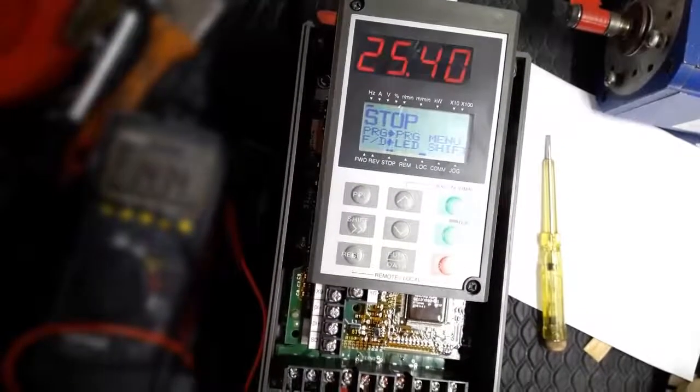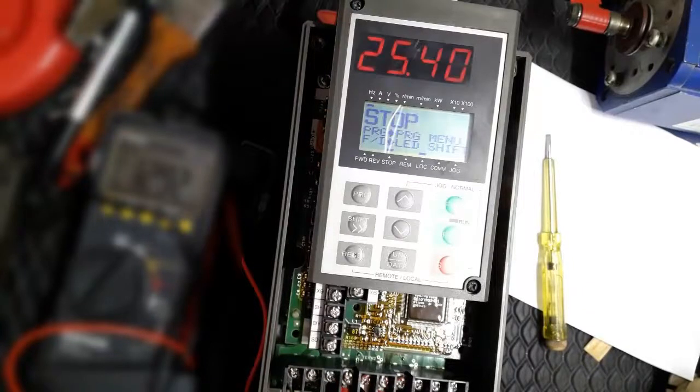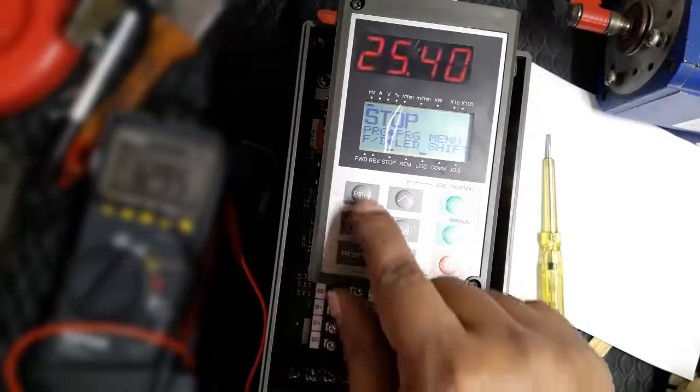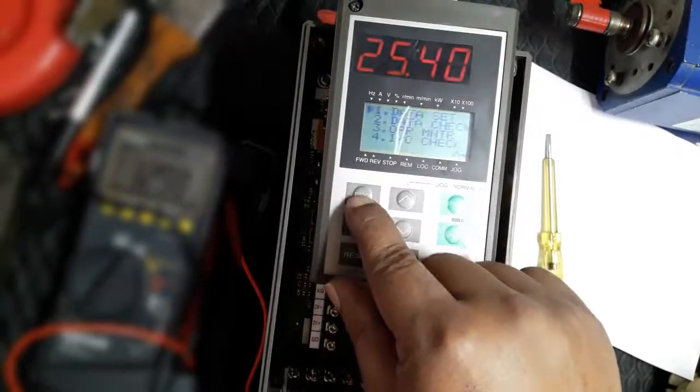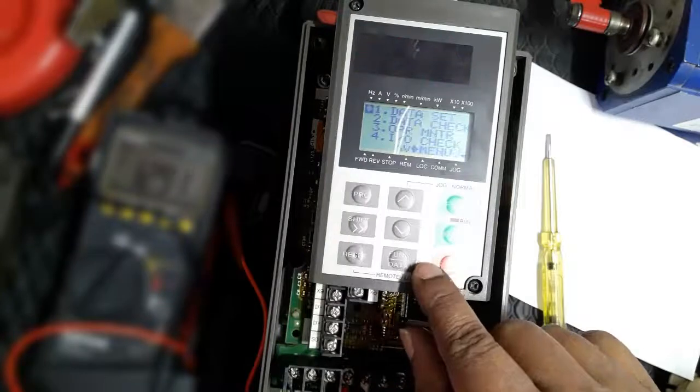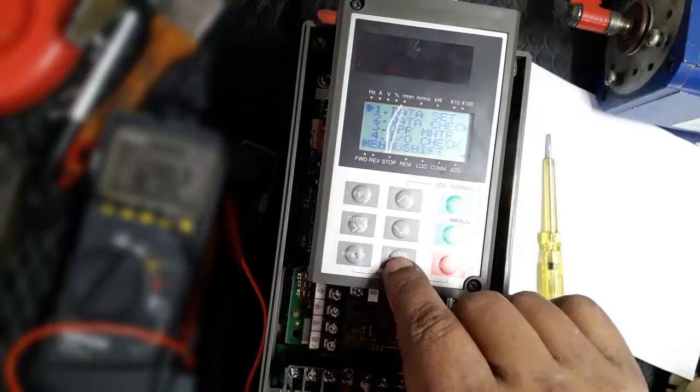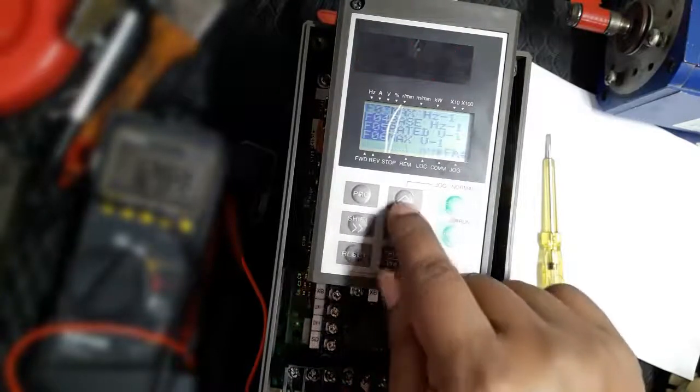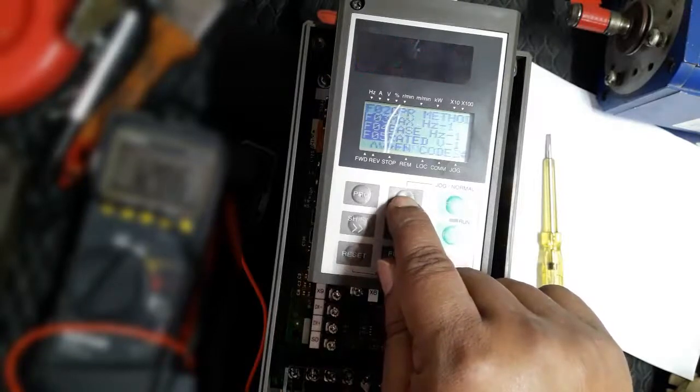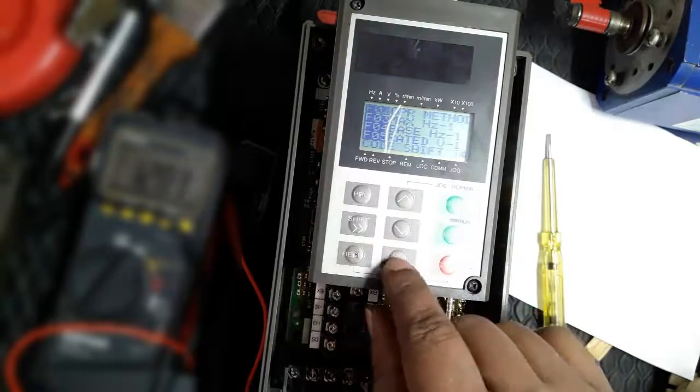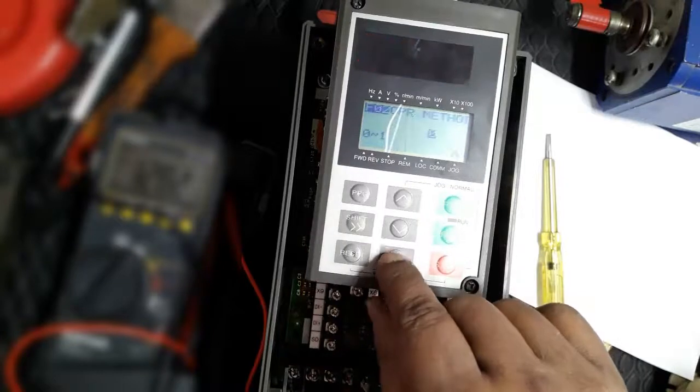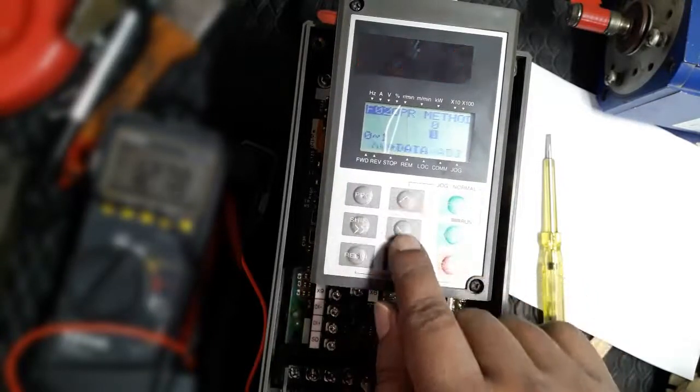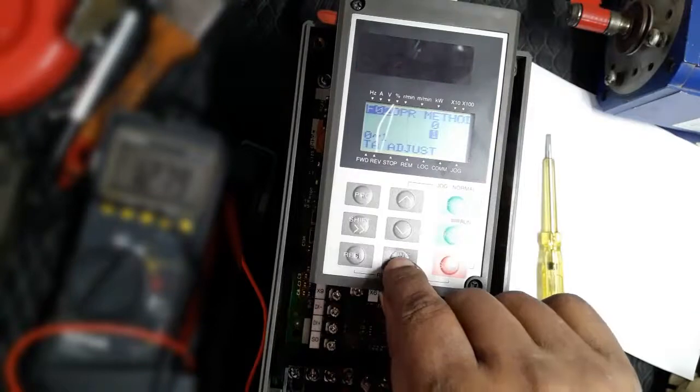We want to externally operate the Fuji 5000 G11 inverter. First, we need to set the parameters. We set the frequency command and run command in external mode, also called remote mode. Here we set the operation method.